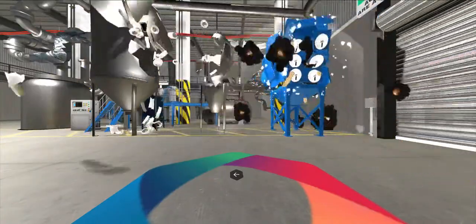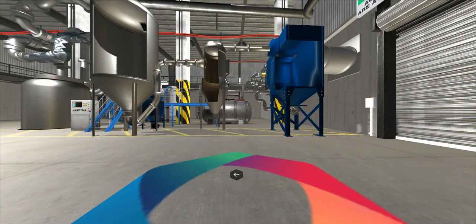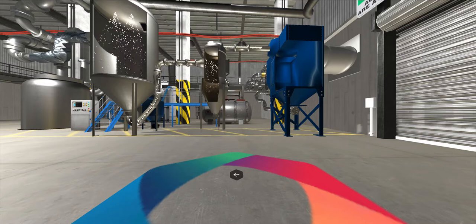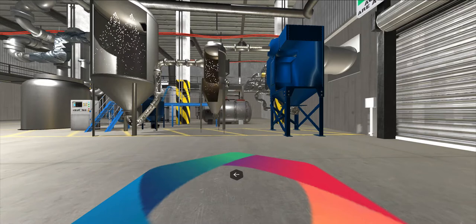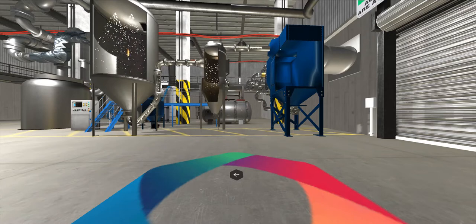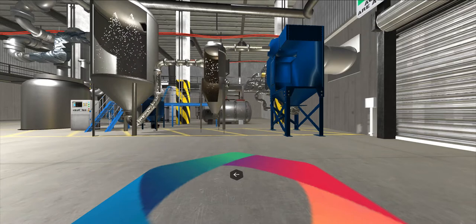The process appeared to be operating normally, but every ingredient required for a dust explosion was present. First, we had fine dry dust. When this fuel was combined with oxygen and dispersed in a confined vessel, all that was needed was an ignition source — and in this case, an upset condition in the form of an exothermic reaction from material buildup in the spray dryer created the ember.